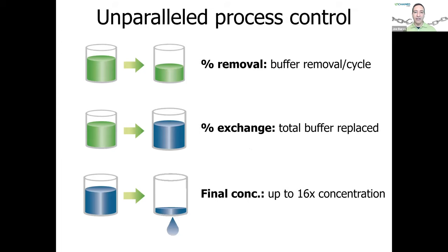By automating it, you get a lot of control over your process. You can control percent removal per cycle — if you have low protein concentration you may completely drain the well, whereas at high concentration you may do smaller replacement per cycle. For percent exchange, you can stop at a low percent exchange like 96%, or go higher to 99% or above. For concentration, you don't have to concentrate to the initial volume — you can concentrate up to 16-fold, or just concentrate without any buffer exchange.